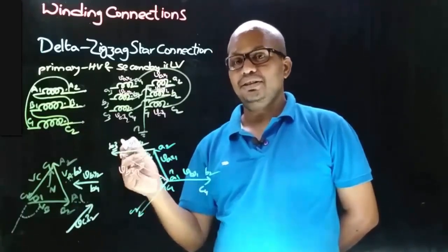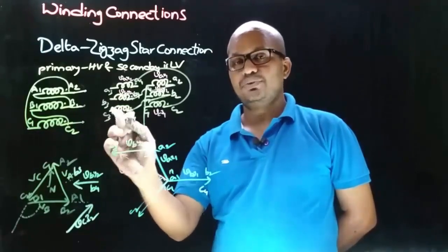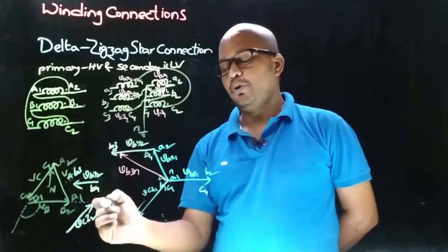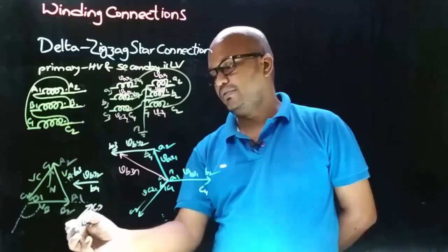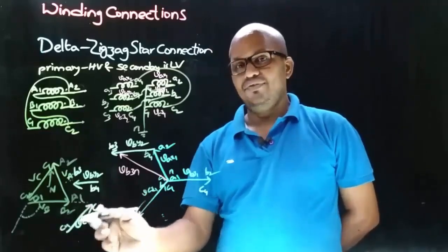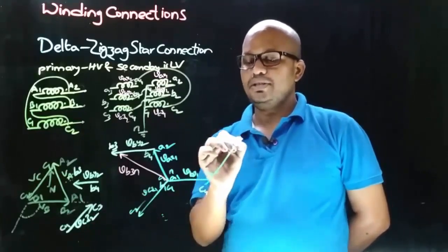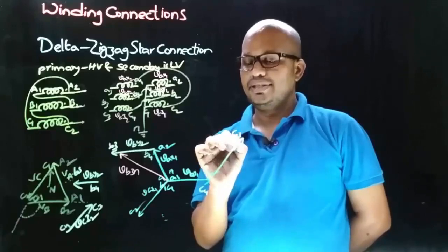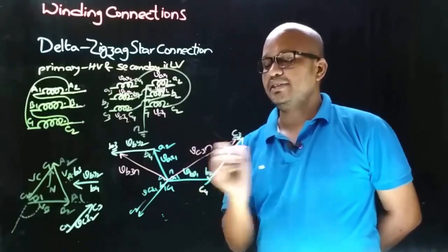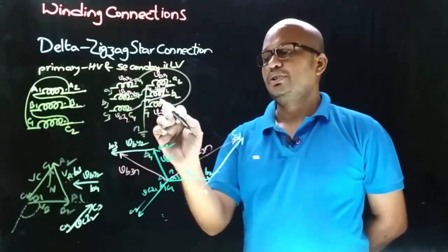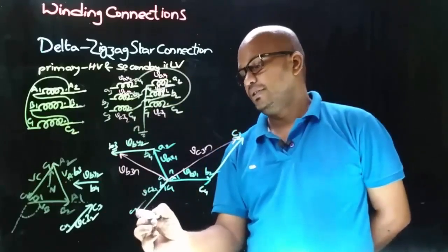And now we need to decide the terminals of the VC-Z2 phasor. The terminals are C3 and C4, and the connection is taken from the non-dot end, meaning the arrow will point towards the connection we took from, that is C3, and the other end will be C4. Now draw this VC-Z2 phasor such that B2 will have the C4 connection, meaning the phasor diagram is like this. This is C3. Therefore the resultant voltage is VC3N. And now in this winding connection, to the dot end C2 there is an A4 connection, meaning to C2 there must be A4.